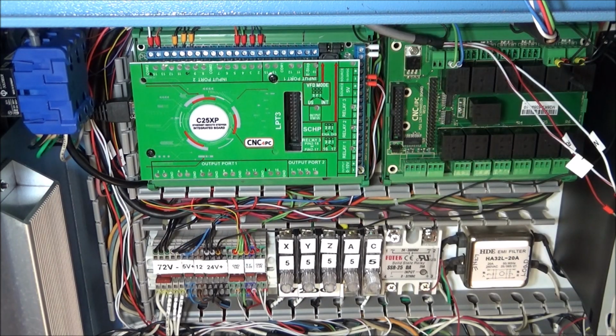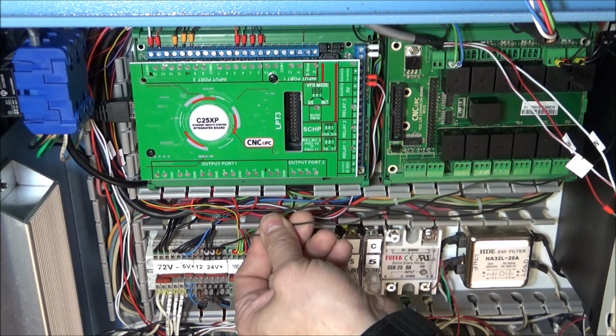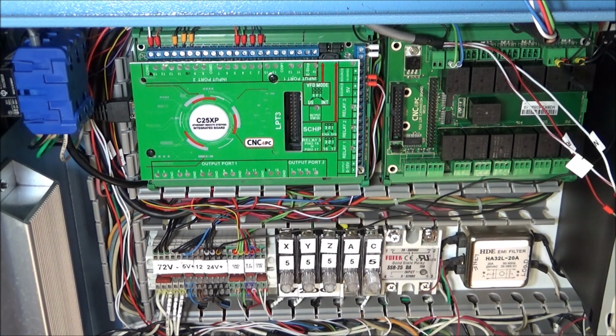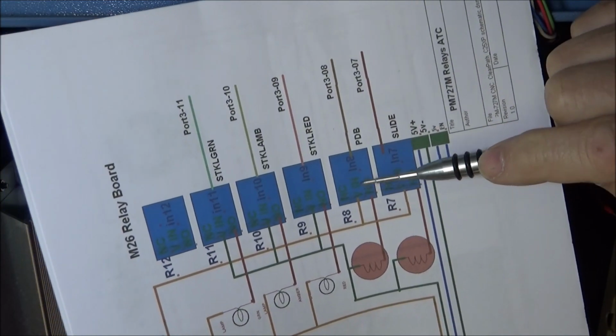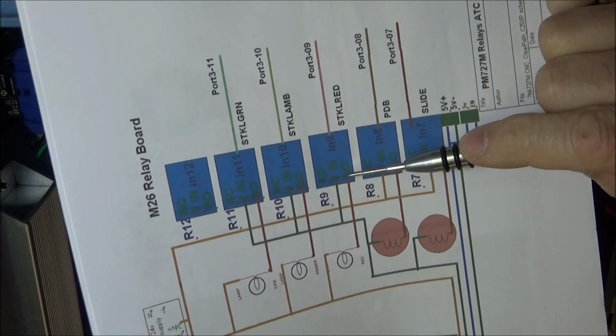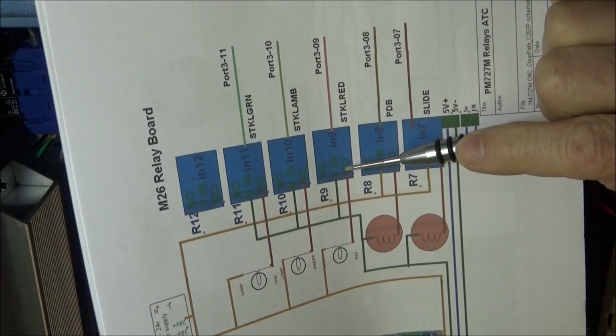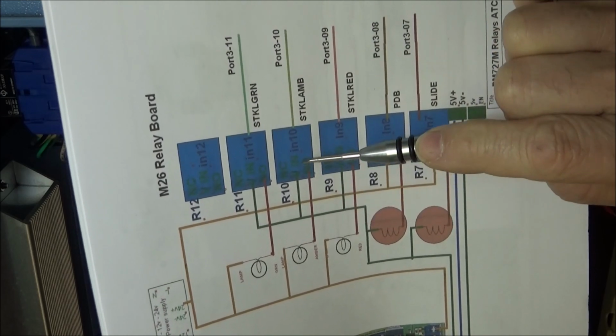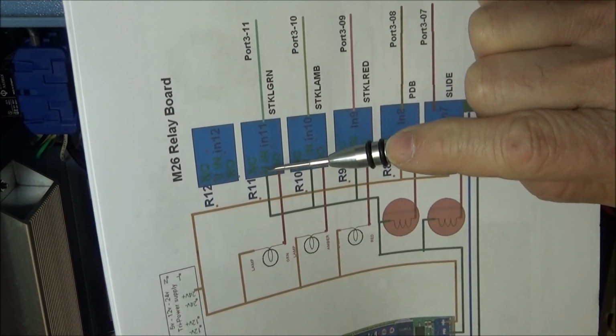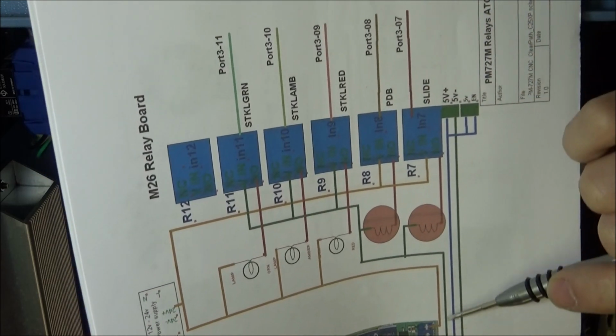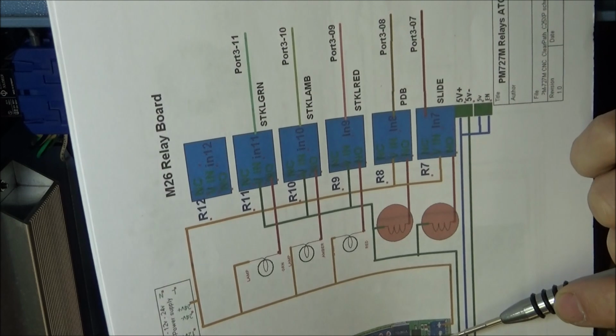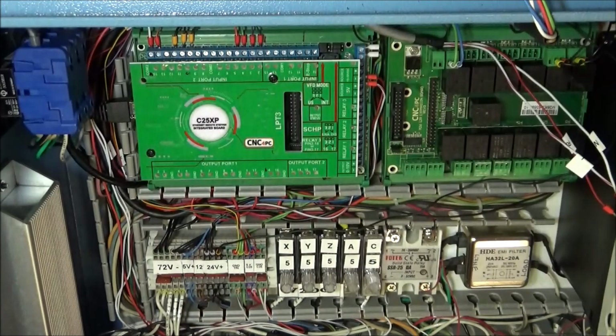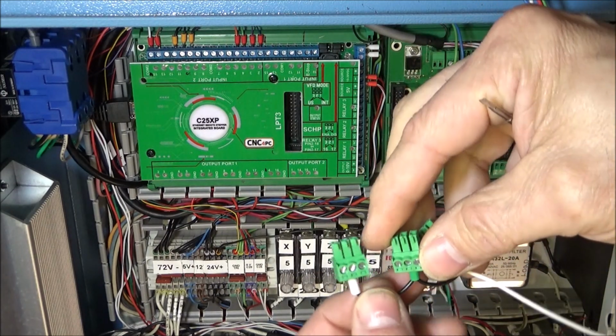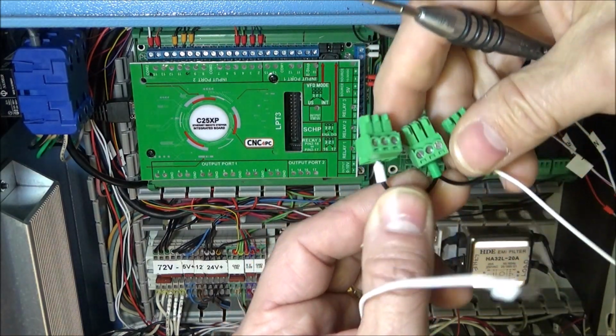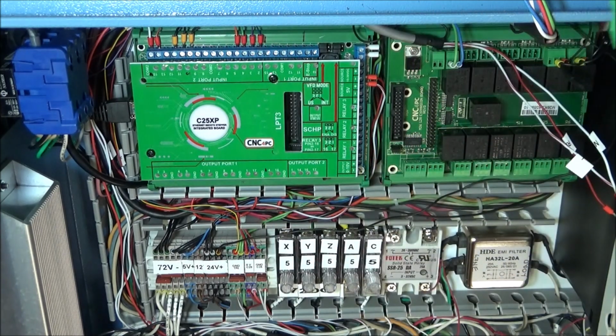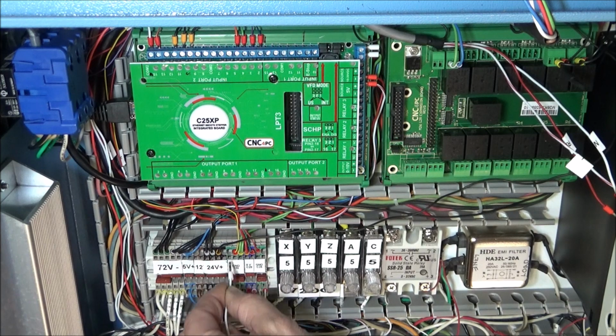Alright, so the stack lights are wired just a little bit different. Now that we have our power landed, we're going to wire in our returns. Now the returns are going to be switched with the relays. So we're going to go out from our normally open over to each lamp. And then on our voltage in, we're really just providing a common. And the common is going back to our 24 volt tri-power power supply. So what I've done is I've just made up this little jumper here to go from one relay to the next, and this is on the voltage in terminal, and then this is going to go over to our tri-power ground here.